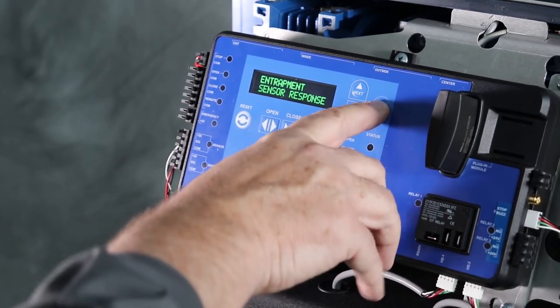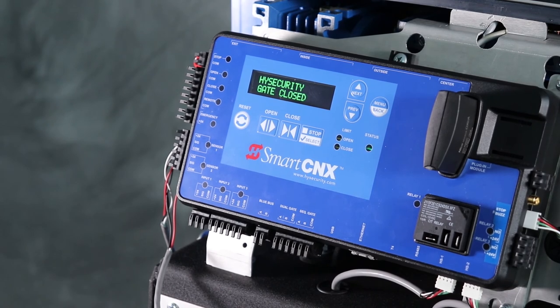Now the PhotoEye will chirp if the beam between them is broken, and it'll chirp twice if the beam is restored. You can use these chirps to line up the PhotoEye. I'll just show you — I'm breaking the beam with my hand, and as I pull my hand away you get the two chirps.